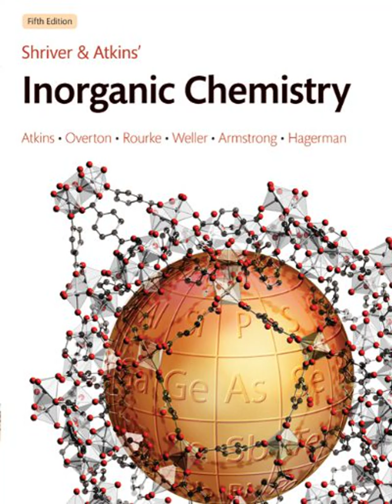What does that produce? All the carbon becomes CO2, all the hydrogen becomes H2O, and the nitrogen becomes N2 gas, possibly with some nitrogen oxides, NOx. Then you measure those gases. Yes. The mixture of gases is swept by a carrier gas, usually helium, through a reduction furnace containing hot copper. This removes any excess oxygen and converts any NOx back to N2. Then the gases pass through a series of detectors, often thermal conductivity detectors, which sequentially measure the amounts of H2O, CO2, and N2. And from that, you get the percentages.